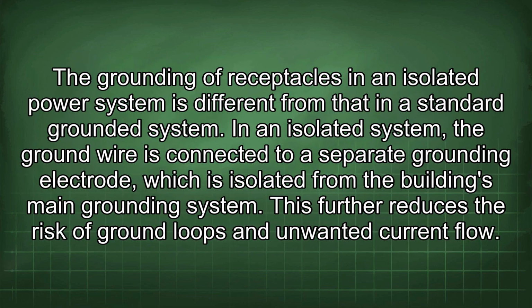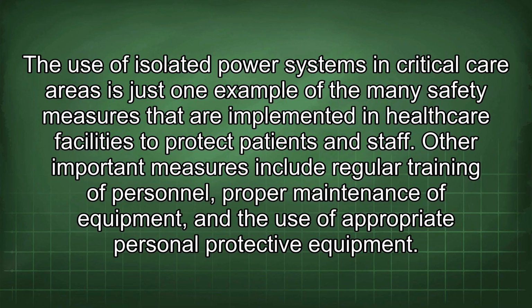The grounding of receptacles in an isolated power system is different from that in a standard grounded system. In an isolated system, the ground wire is connected to a separate grounding electrode, which is isolated from the building's main grounding system. This further reduces the risk of ground loops and unwanted current flow. The use of isolated power systems in critical care areas is just one example of the many safety measures that are implemented in healthcare facilities to protect patients and staff.